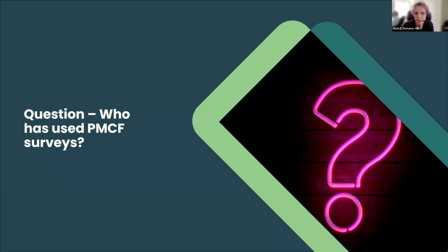So if you're going to go down that approach, you're going to have to justify it and ensure it falls under that high quality level 4 survey if appropriate. To Sean's question, you can use this data to support safety or clinical performance. Whether or not it's considered substantial or pivotal is another issue, but there's nothing to prevent you from using it. The quality level impacts how important it is to the particular device and its relevancy in terms of conformance to safety or clinical performance.